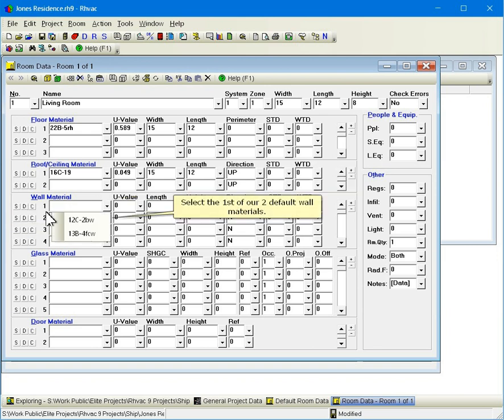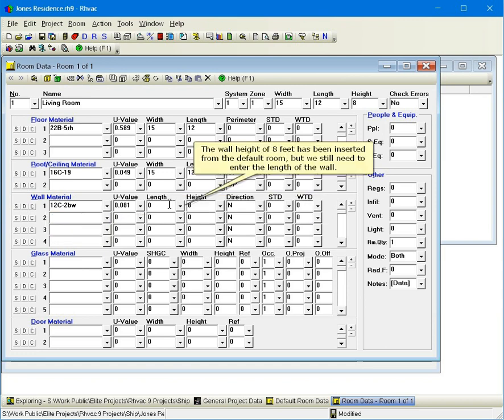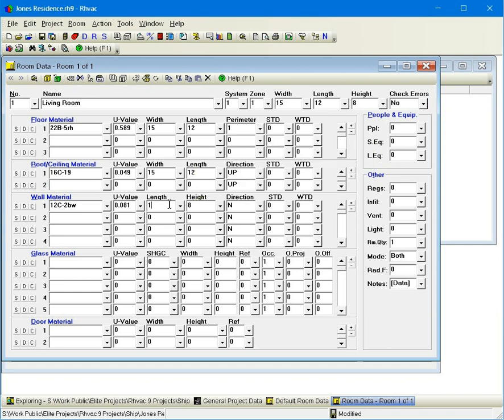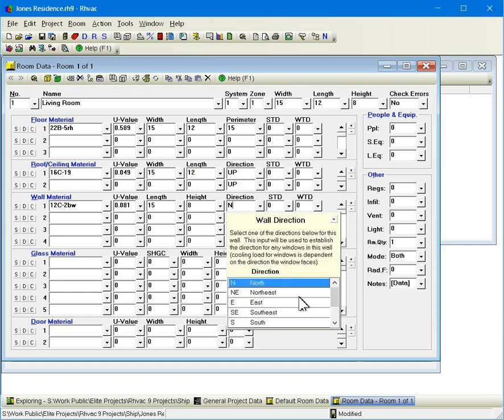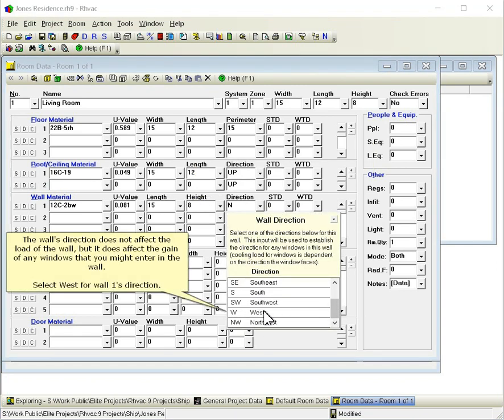Select the first of our two default wall materials. The wall height of 8 feet has been inserted from the default room, but we still need to enter the length of the wall. The wall's direction does not affect the load of the wall, but it does affect the gain of any windows that you might enter in the wall. Select west for wall 1's direction.